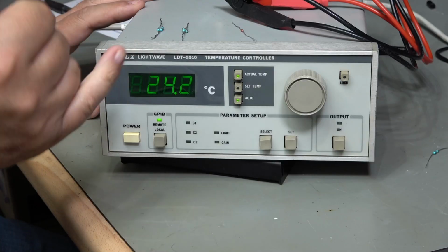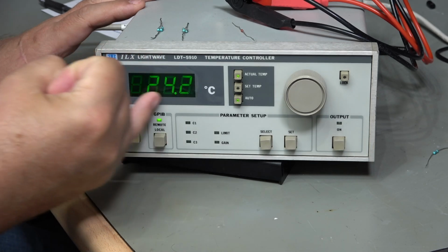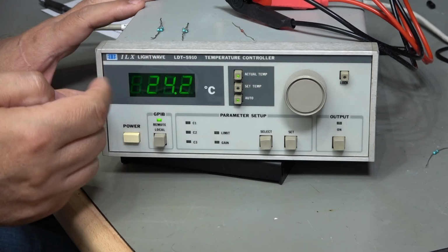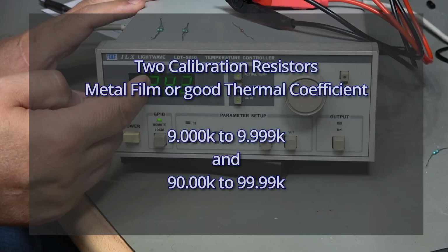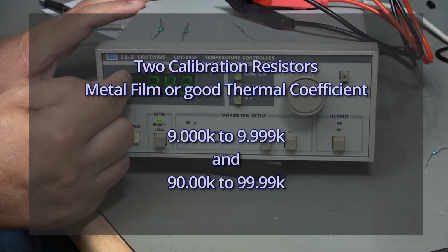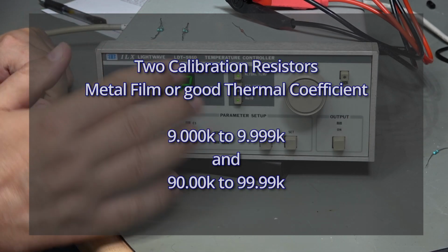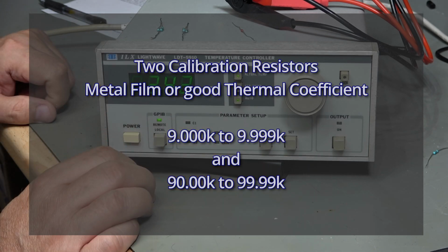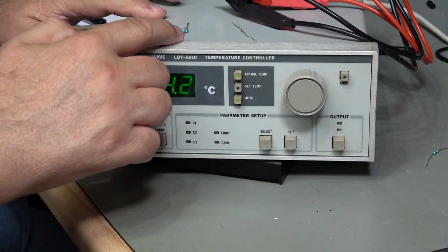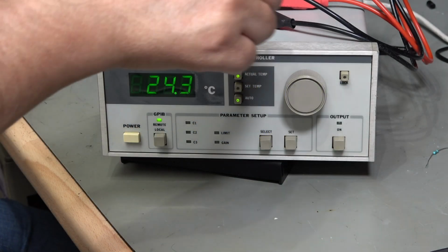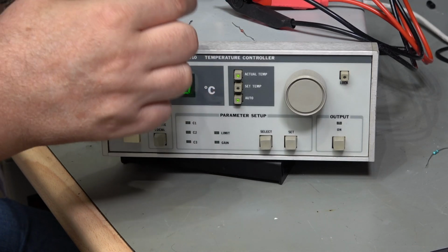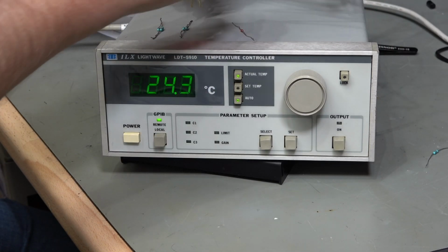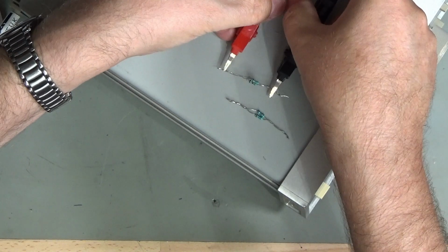To do that, we use two known resistors. We want to use pretty much the full range, the 4 digits that we have available. We need something between 9 and 9.999, or 90k and 99.9k. So something in those regions. It doesn't actually matter what they are, because we're going to measure them accurately first. Thermally stable metal film resistors. So what I'm going to do is measure these resistors. I'm just going to write those down. This is a 4-wire resistance measurement on a 6.5 digit calibrated meter.